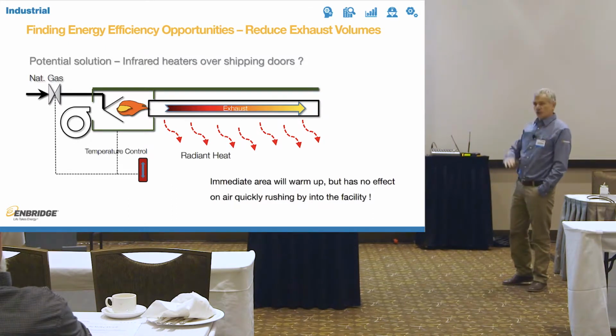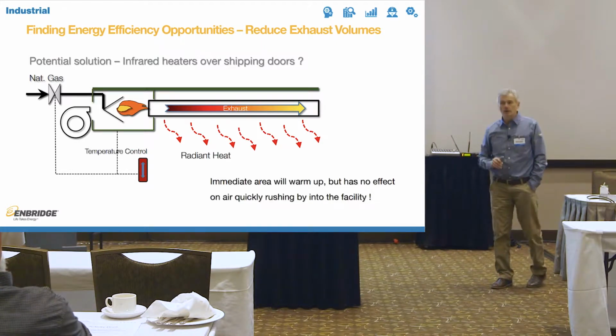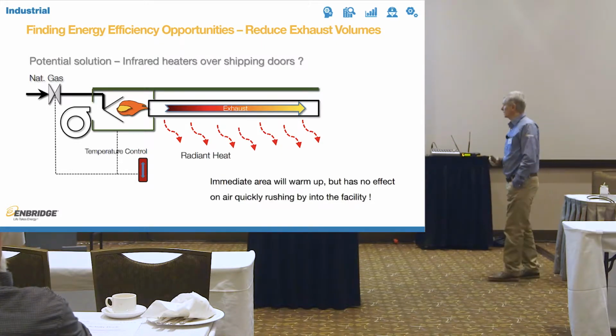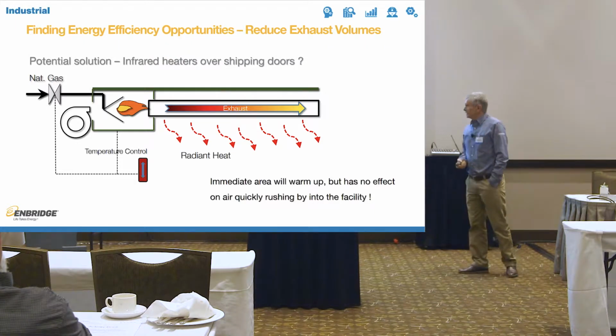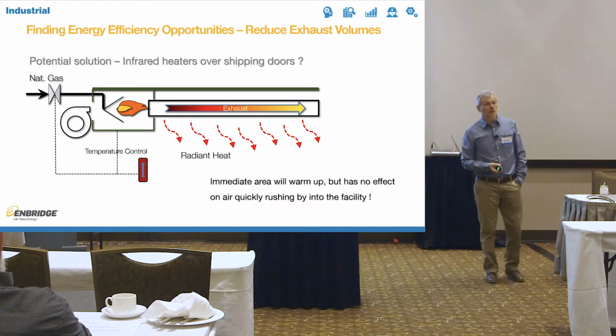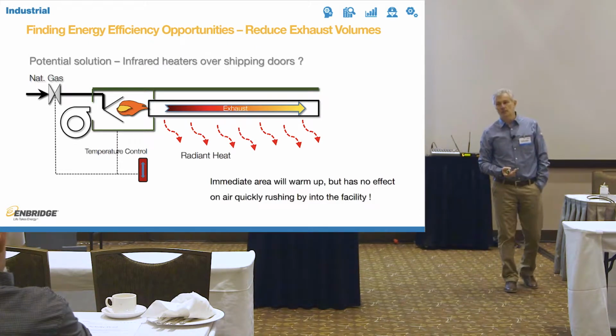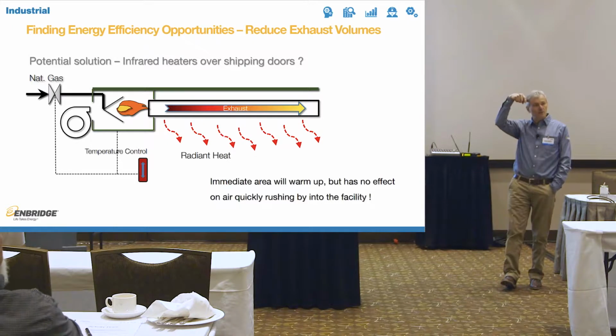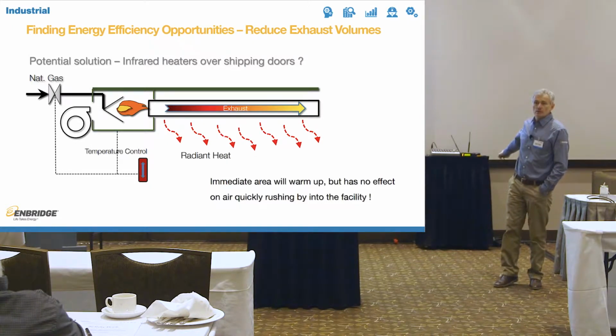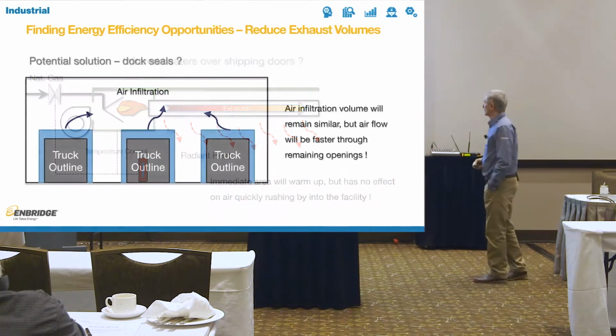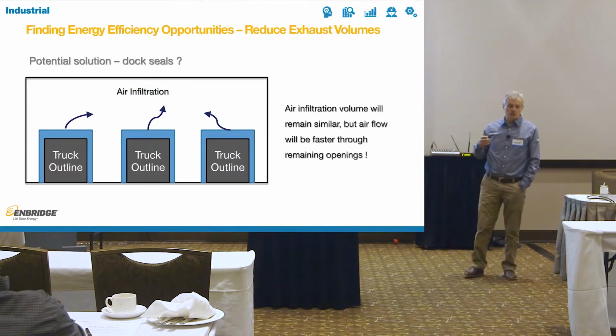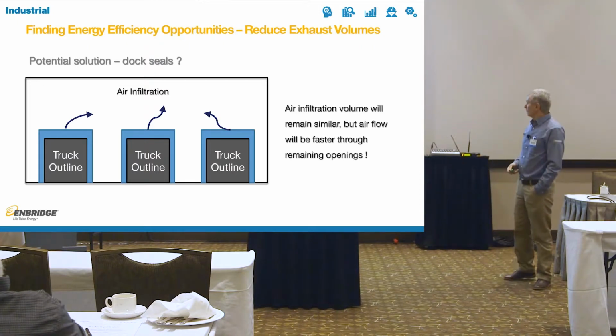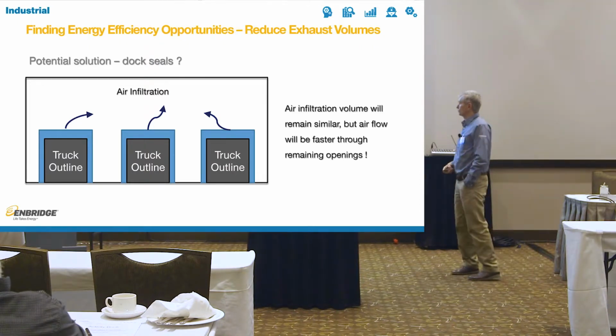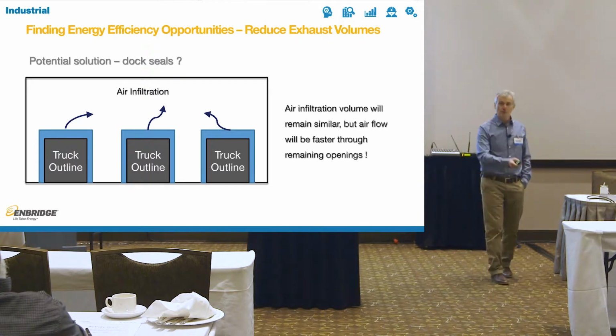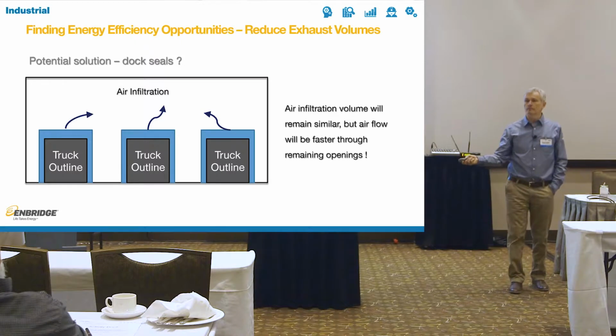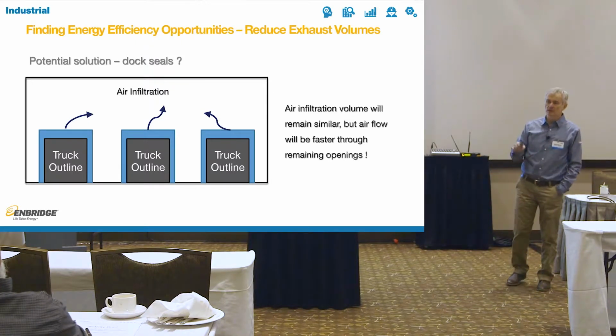So we look at infrared. You put it over the shipping doors. It's a nice, neat solution. Not too much cost, not too much hassle. It gives us radiant heat, but what the heck does it do for 10,000 CFM of air that's just blasting along? Absolutely nothing. So the guy standing right under it is warm, but the guy behind him is still cold. And you spent the money to install this. So then we go, okay, we have shipping doors, we'll put in dock seals. Yeah, okay, we'll put dock seals on 2 of the doors. The third door will be open, and now all of that volume of infiltration air will come through the third door. You solved, again, nothing. You spent the money and solved nothing.